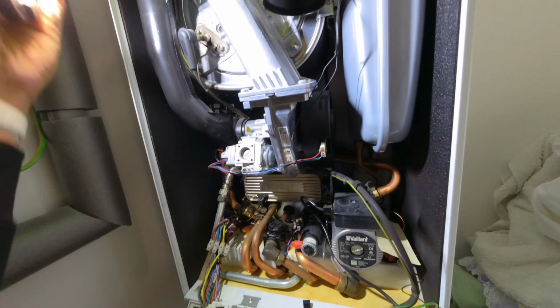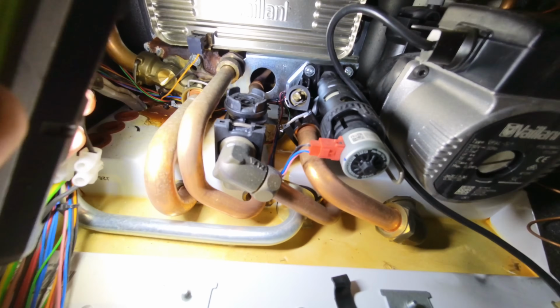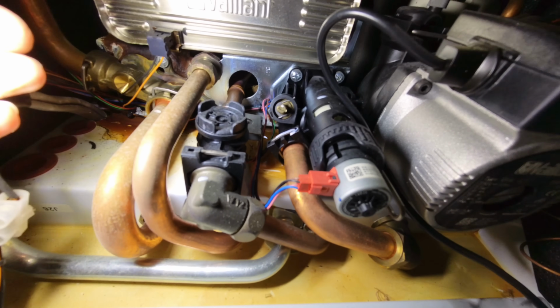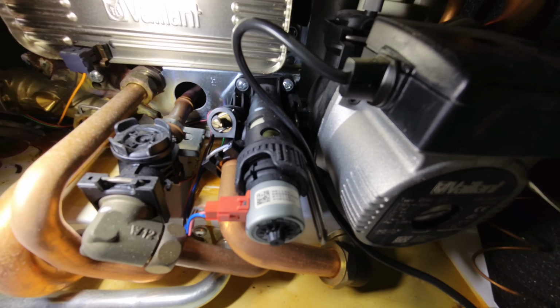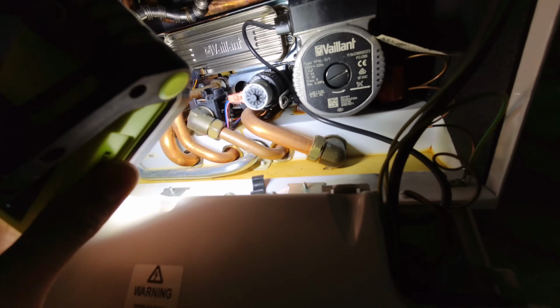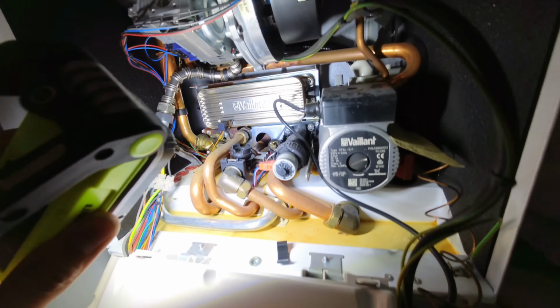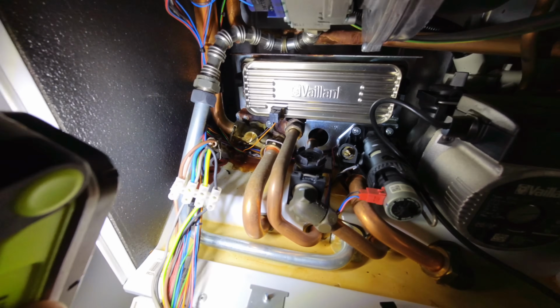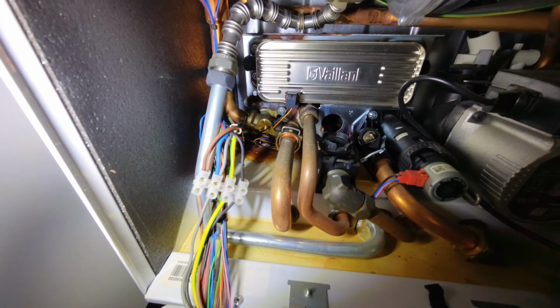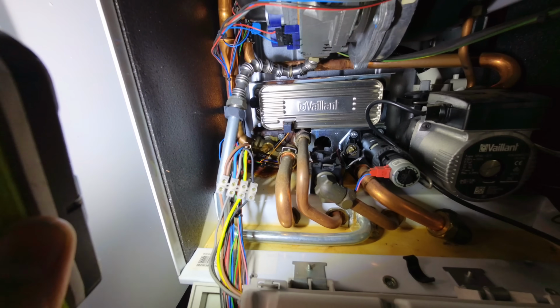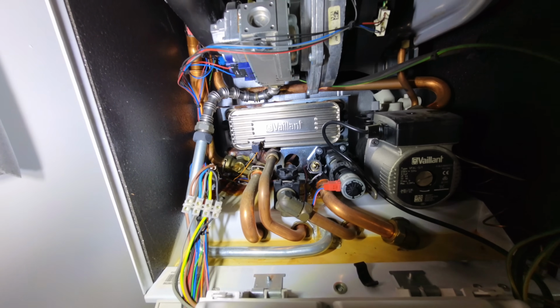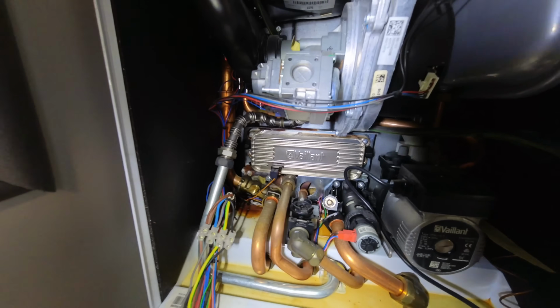Now, first thing you may look at where the water's pooling, you may be mistaken that it's the diverter valve. But the diverter valve is all looking good, there's no signs of any leaks on it. If you follow that rusting round, you might think it could be the plate heat exchanger. You follow it up, there's signs of rusting there, still nothing there. But let me just try and tip this camera back a bit, so let's try and get in there.